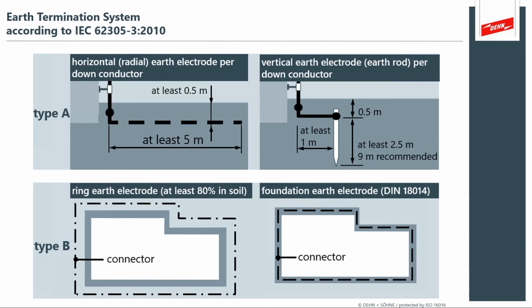And then we talk a lot about the type B ring earth electrode, where it's a grid around the system. We see a lot of this application that looks a lot like a ring earth electrode at power plants, where it's a large mesh, a large matrix of interconnected rings. And then there's a great discussion about foundation earth electrode, which is essentially what you hear a lot as the Ufer ground, which is buried in the local concrete and within the structure, the actual cement and rebar structure. So this is a nice introduction to that, but it's really important because it all ties together with our topics today, where we'll be focusing a lot on bonding as well.